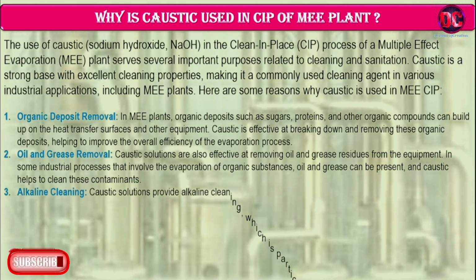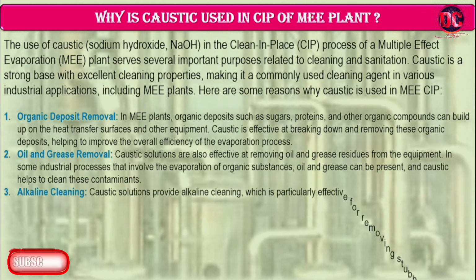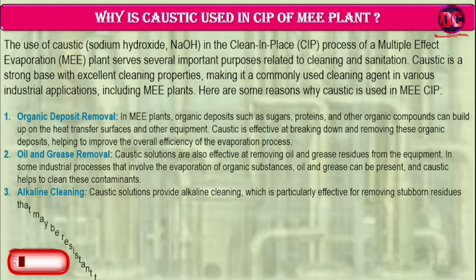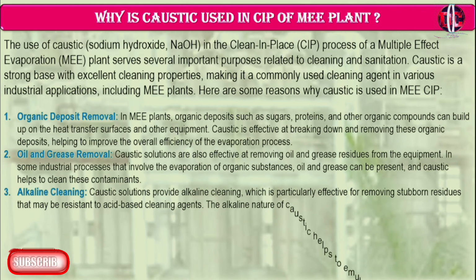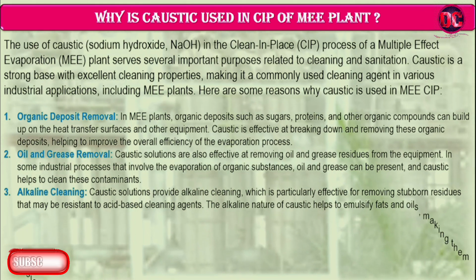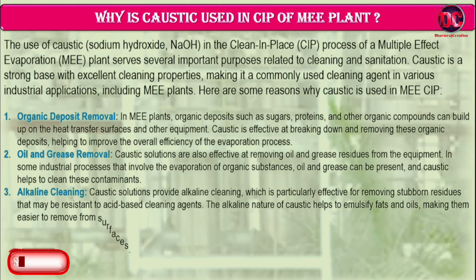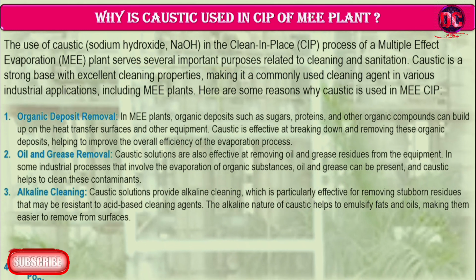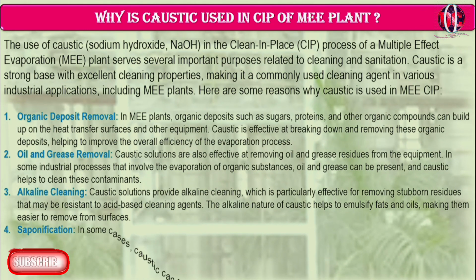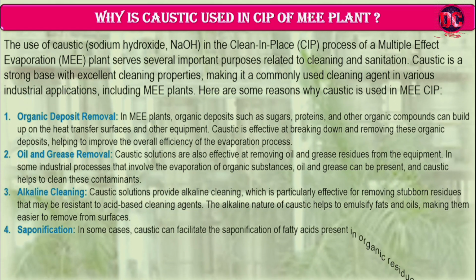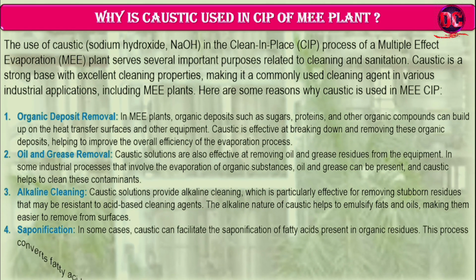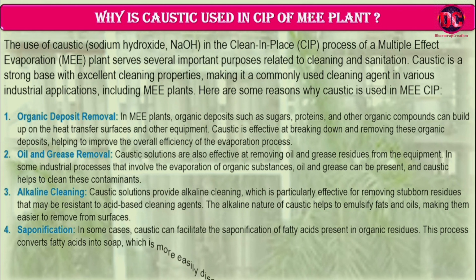3. Alkaline cleaning. Caustic solutions provide alkaline cleaning, which is particularly effective for removing stubborn residues that may be resistant to acid-based cleaning agents. The alkaline nature of caustic helps to emulsify fats and oils, making them easier to remove from surfaces.